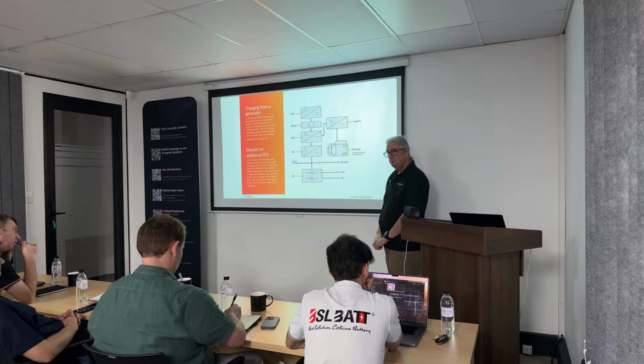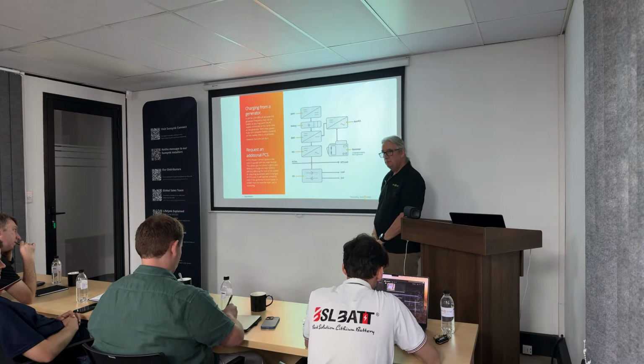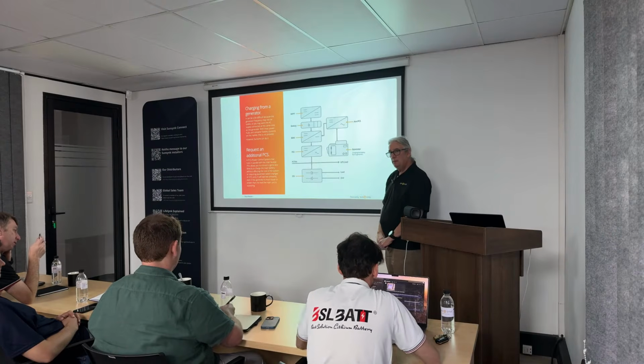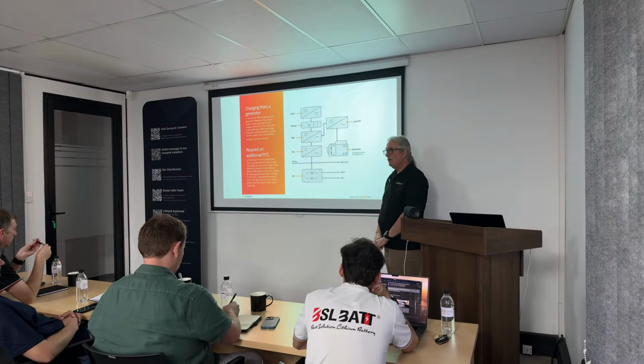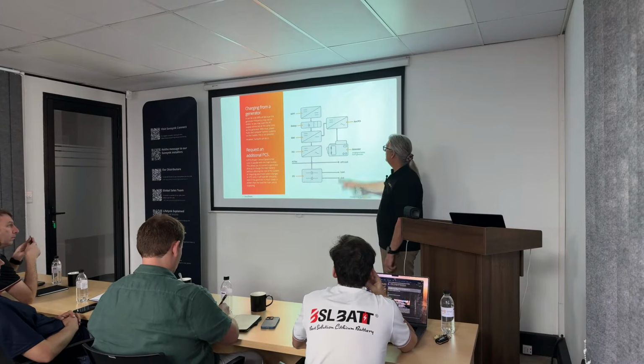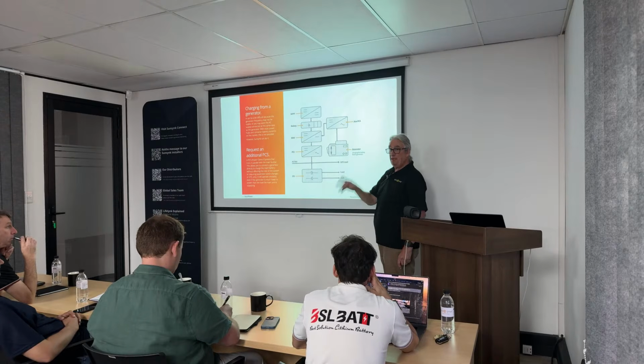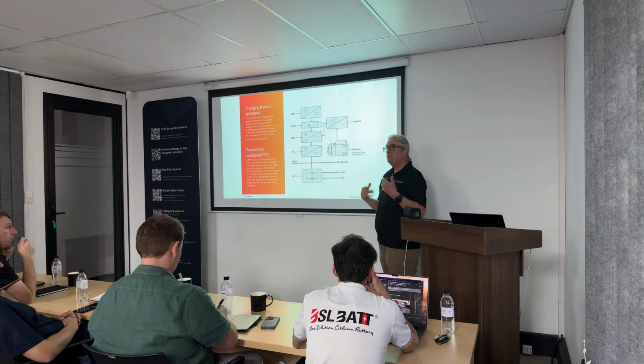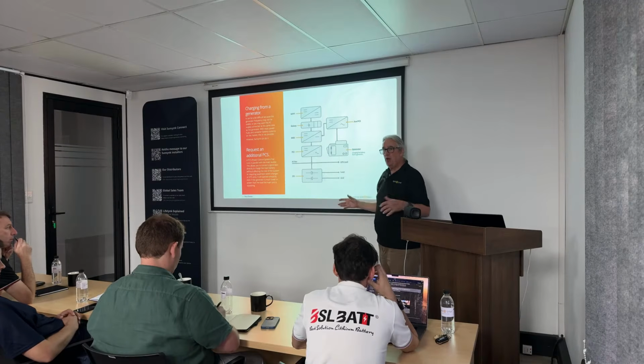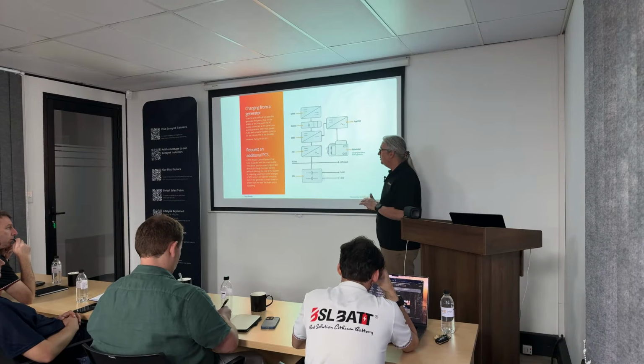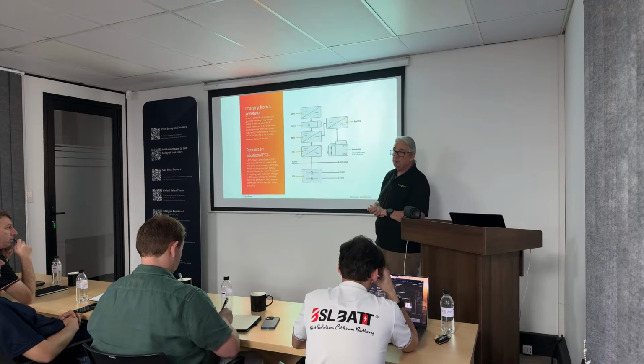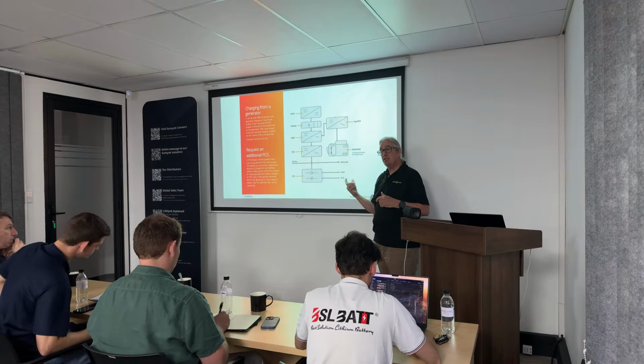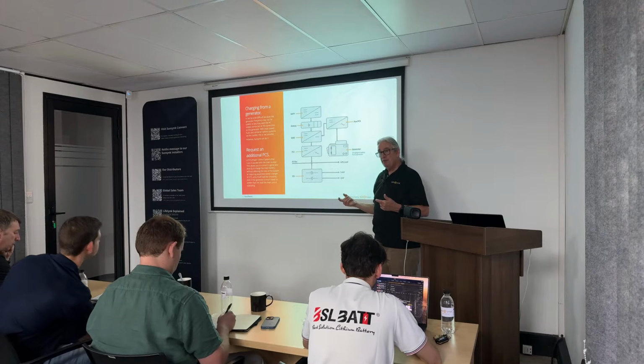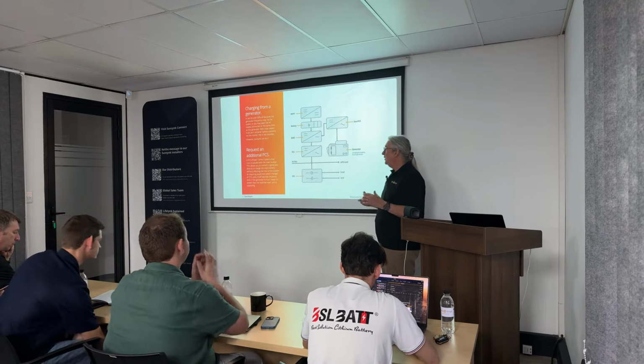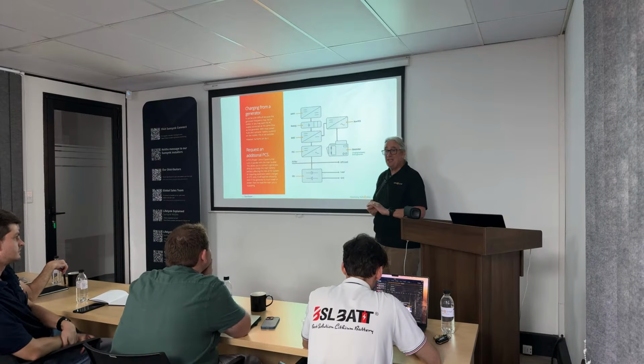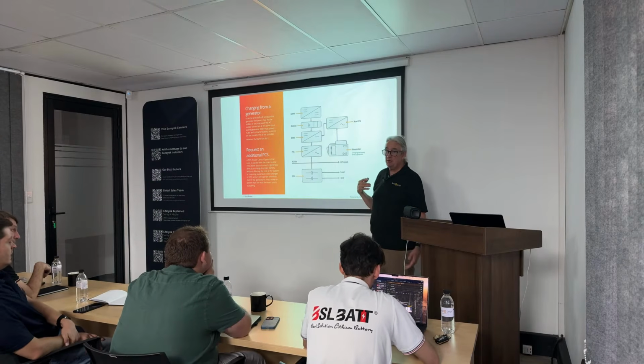And you are wanting to basically use the same AC bus for the generator and also for the grid coming in. Is that possible? If you run it from auxiliary, that is the best way because it's tidy. And I mean tidy in as much as it will get rid of all the noise on the generator. But you can do two ways. One, you can use a static transfer switch if you want to, but it means the unit's got to take the full load of the generator. Or, as most generators have an ATS on them, you can run the AC through the ATS of the generator.